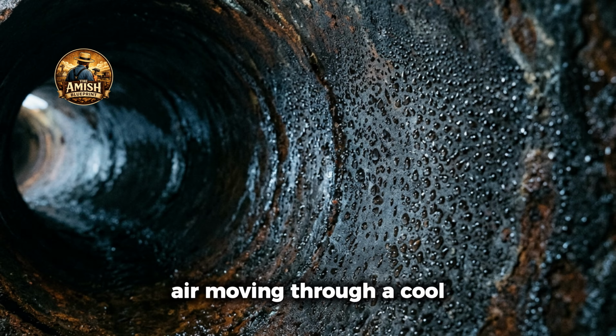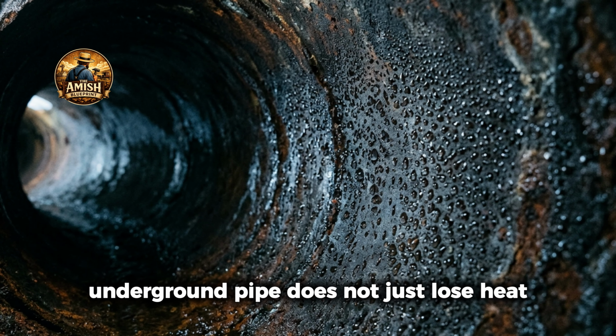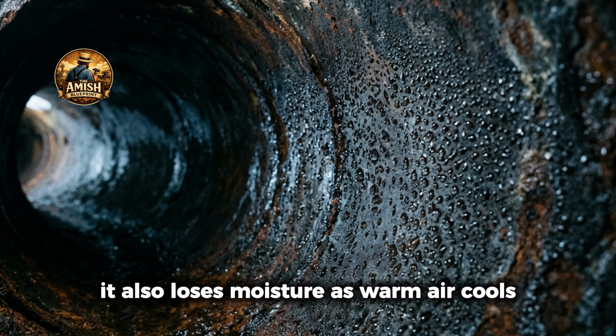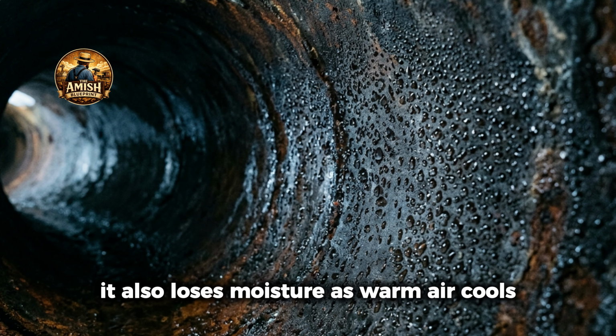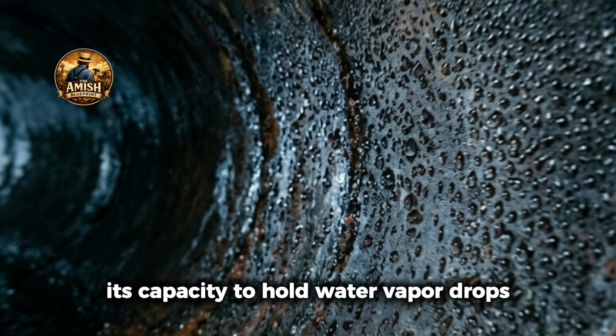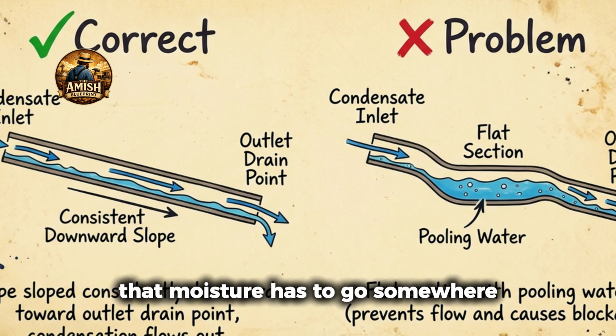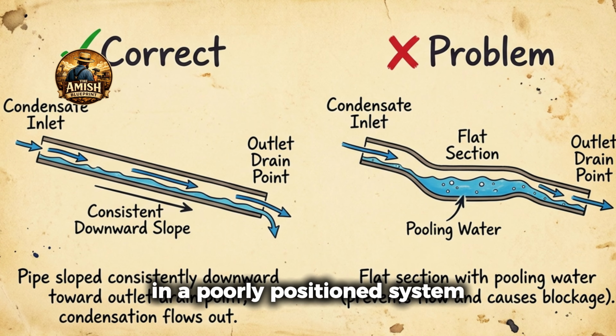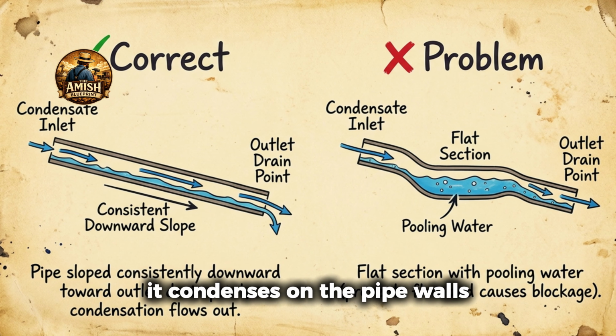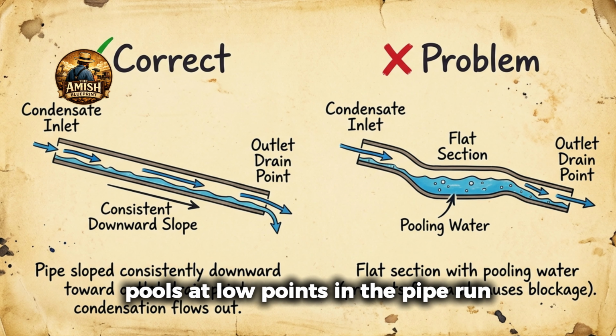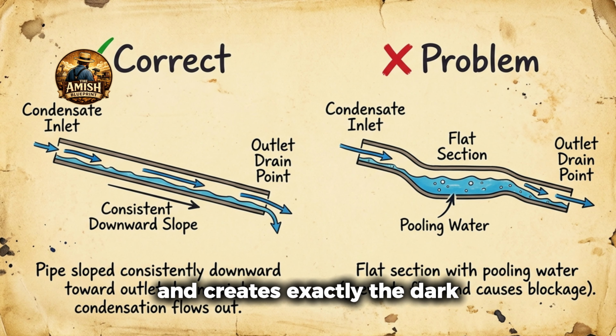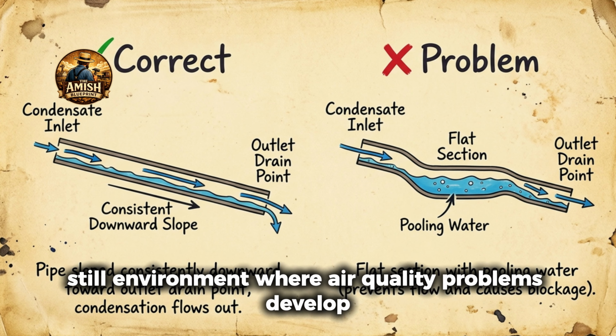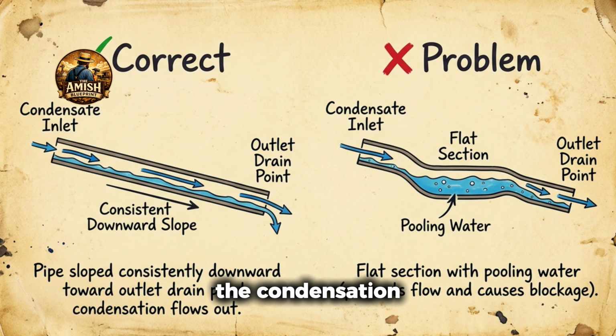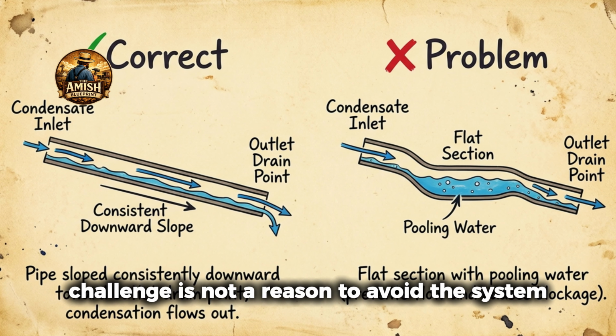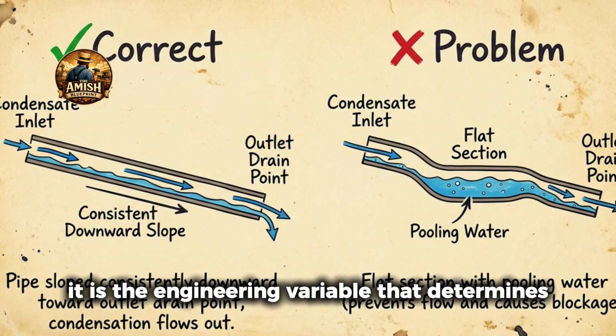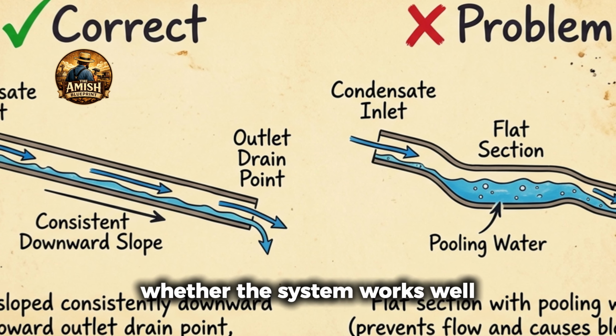Air moving through a cool underground pipe does not just lose heat, it also loses moisture. As warm air cools, its capacity to hold water vapor drops. That moisture has to go somewhere. In a poorly positioned system, it condenses on the pipe walls, pools at low points in the pipe run, and creates exactly the dark, damp, still environment where air quality problems develop. The condensation challenge is not a reason to avoid the system. It is the engineering variable that determines whether the system works well or does not.